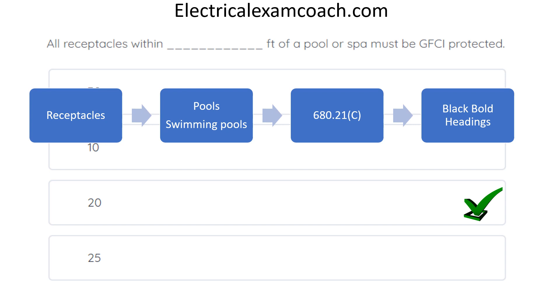I want to note that this does not negate all of the requirements in 210.8(A) and (B), which are your overall requirements for GFCI protection. This is in addition to those. Not only does 210.8(A) or (B) catch you for GFCI protection, but you're also required to do it within 20 feet of the pool or spa.